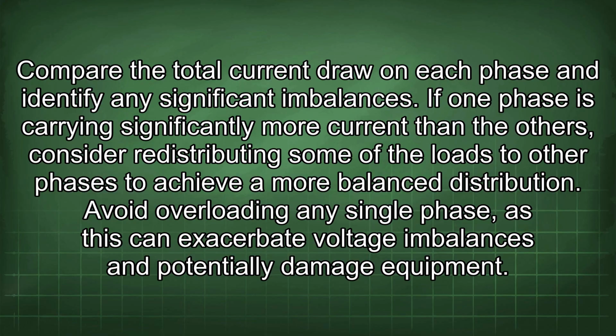If one phase is carrying significantly more current than the others, consider redistributing some of the loads to other phases to achieve a more balanced distribution. Avoid overloading any single phase, as this can exacerbate voltage imbalances and potentially damage equipment.